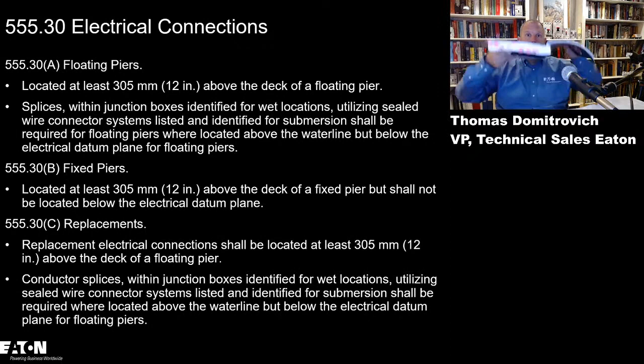555.30 talks about floating piers. Remember, that floating pier goes up and down. You need to be 12 inches above the deck of a floating pier for any of your electrical equipment. So yes, that pier is going to be floating up and down, but you want to be 12 inches above that floating pier. Fixed piers, you have to be 12 inches above the deck, and you cannot be below the electrical datum plane.